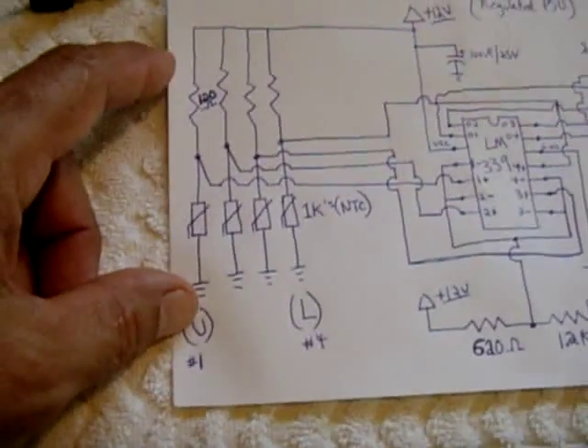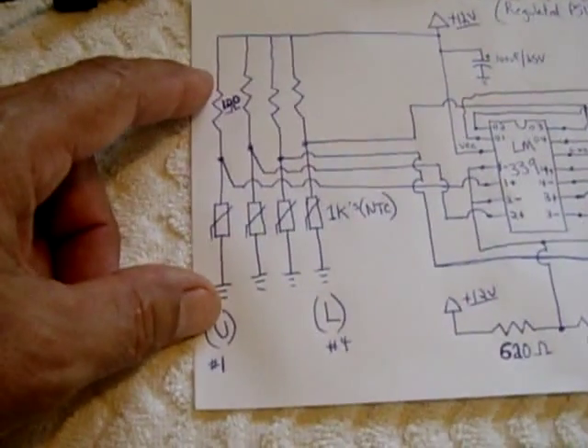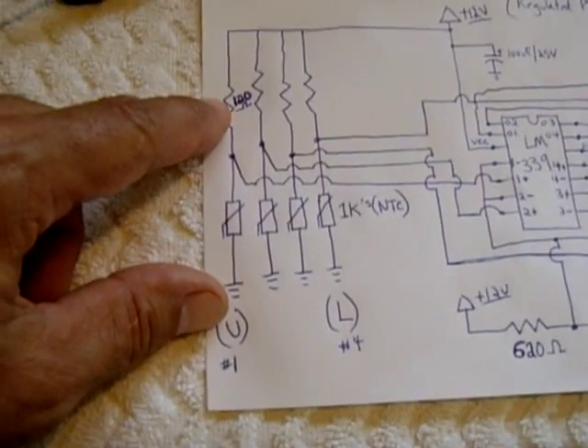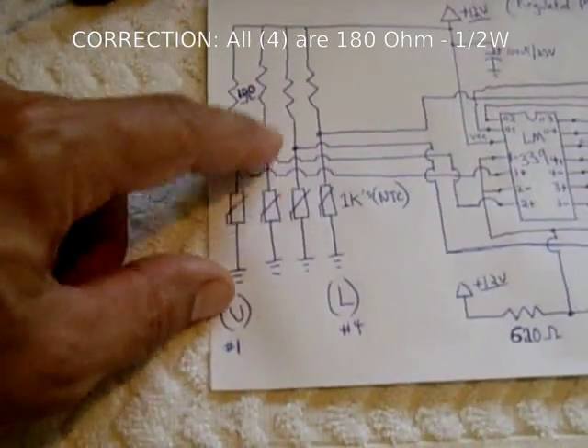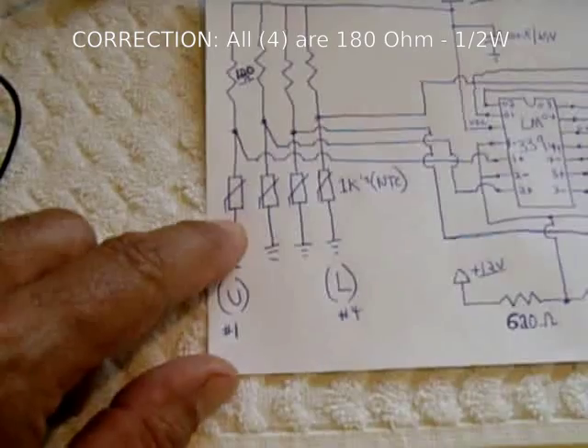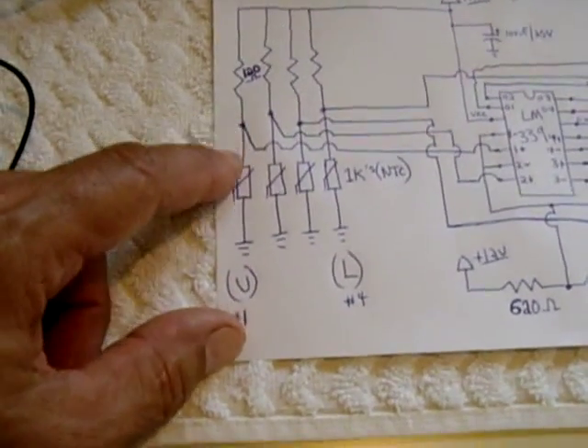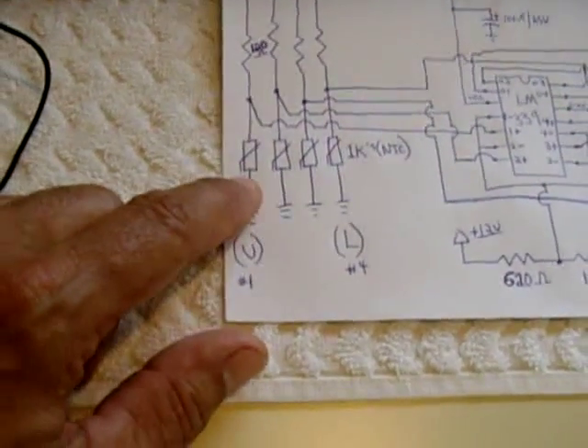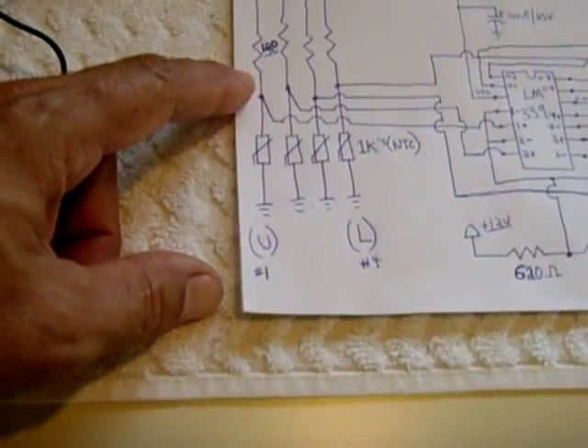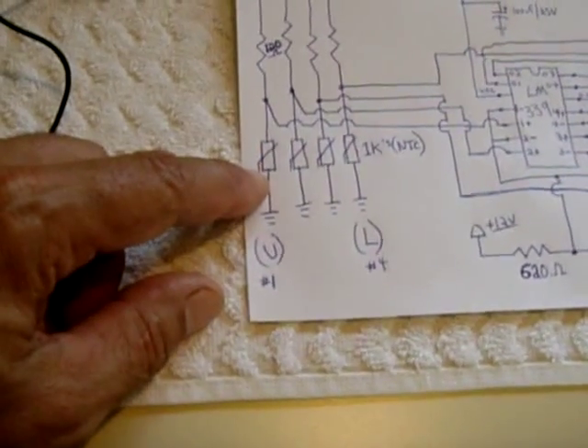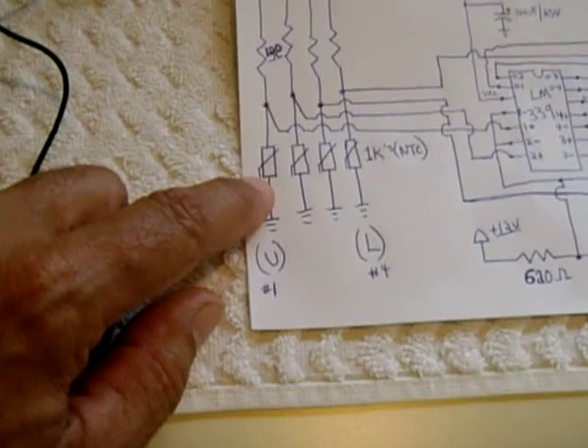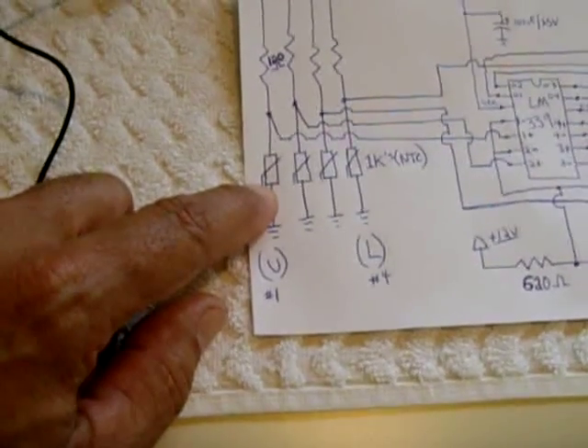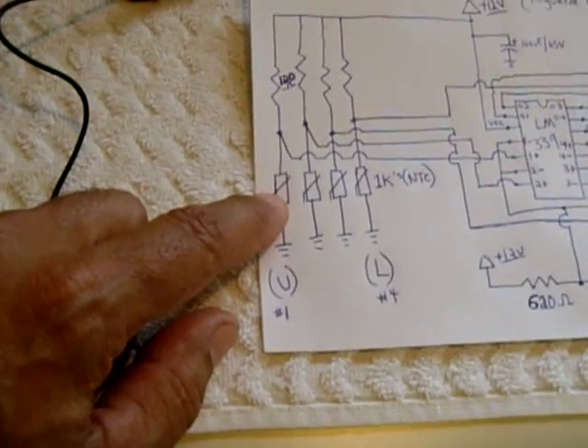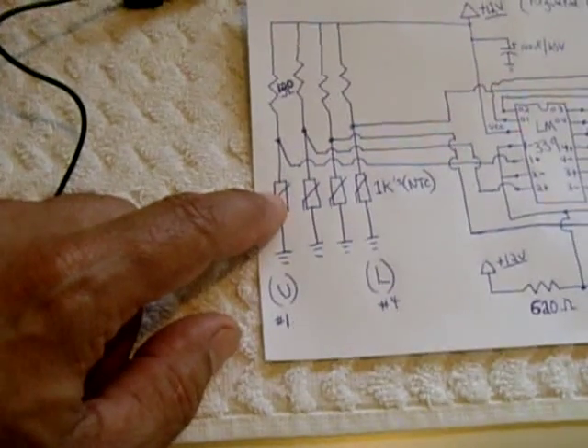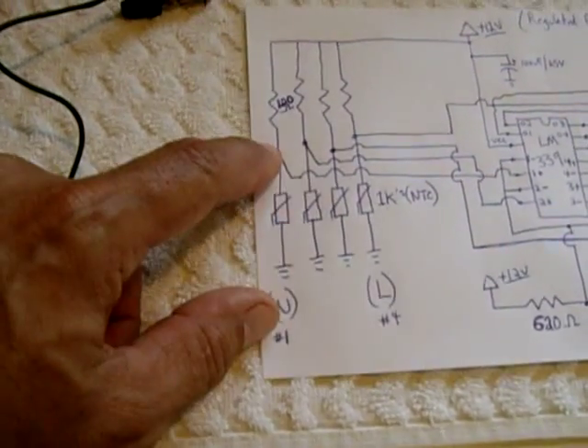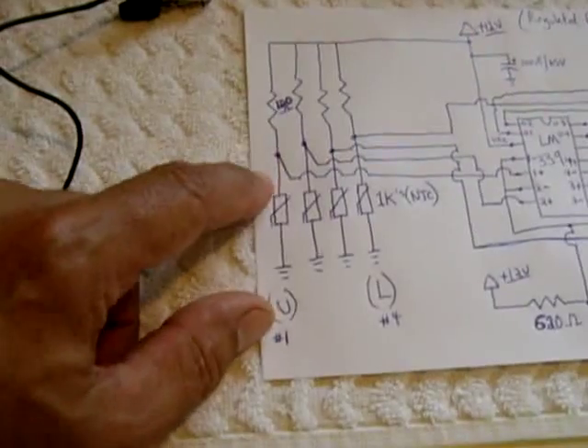In this case, what's going on is you're going to supply a small current. We're going to have a 120 ohm resistor going to each one of these thermistors, and they're going to feed through each thermistor to ground. And what's going to happen when this current flows through the thermistor is it's going to generate heat. These aren't going to get hot, but they're going to get very warm. When they get warm, the resistance value is going to decrease, causing the voltage that was here to drop.